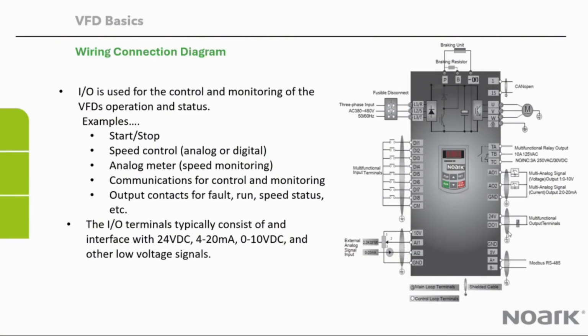We also have a Modbus communication that is standard on the drive, RS-485, that the drive can be wired to a PLC or a SCADA system or something and be told when to start, when to stop, when to run, what speed to run. If I'm faulted, what my current output is. You can gather all the data out of the drive and bring that back to another system. And like I said here, communications is for control and monitoring.